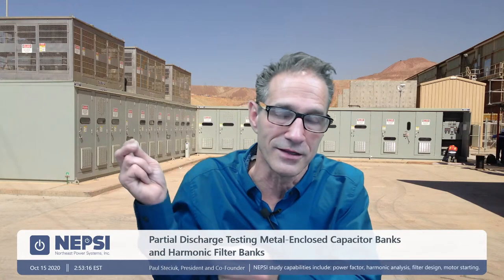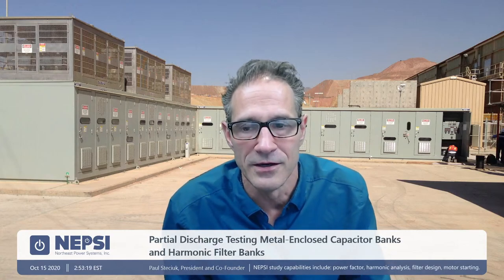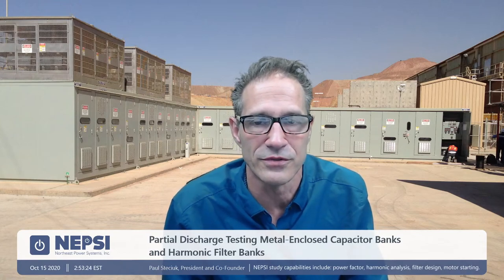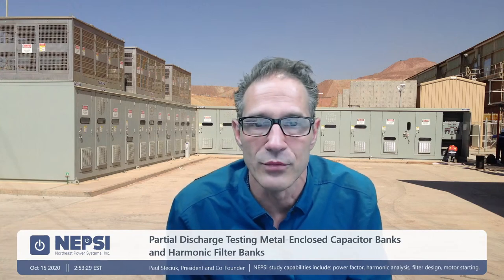Sometimes we're disconnecting one stage at a time. On this last project, when they had the breaker that was left ungrounded, they ended up opening up the disconnects and they located which stage it was on. And then at that point, they identified the breaker. So we might start disconnecting, trying to isolate at that point. But it can be very difficult to find that region where you might be having partial discharge. So that's a good question. At some point in time, we may decide to purchase this other type of equipment to help us locate problems when we do have them, because it can be quite time consuming.